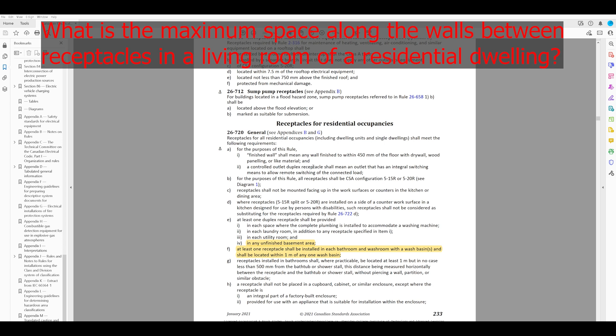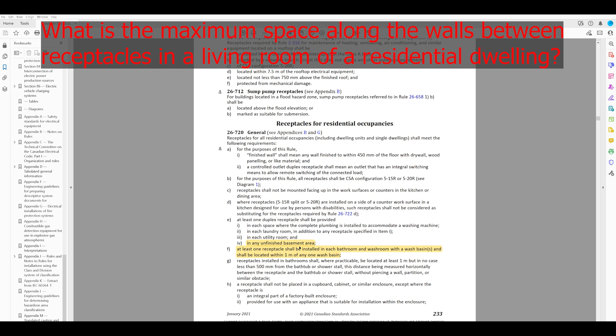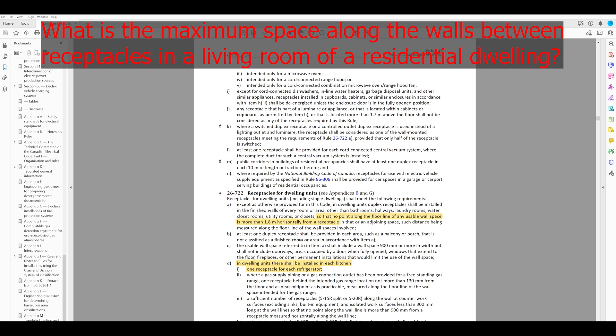We'll scroll through looking for anything about the spacing of receptacles on the wall. We hit the 'General' heading underneath receptacles for residential occupancies — a good place to start. Receptacles for dwelling units shall meet the following requirements: receptacles shall be installed in the finished walls of every room, other than bathrooms, hallways, laundry rooms, water closets, utility rooms, or closets, so that no point along the floor line of any usable wall space is more than 1.8 meters horizontally from the receptacle.